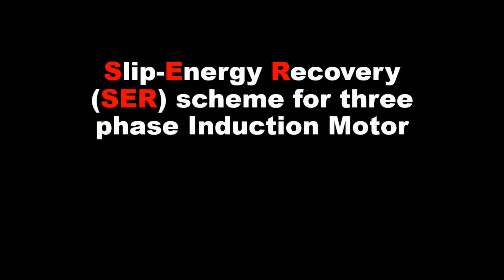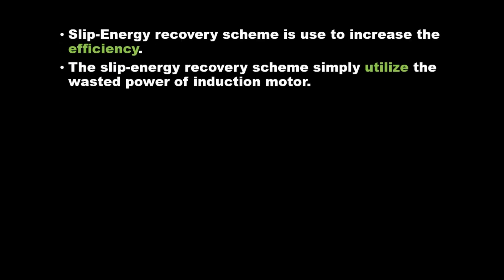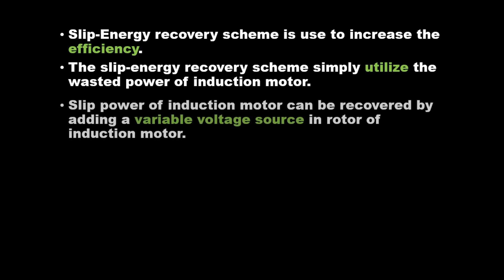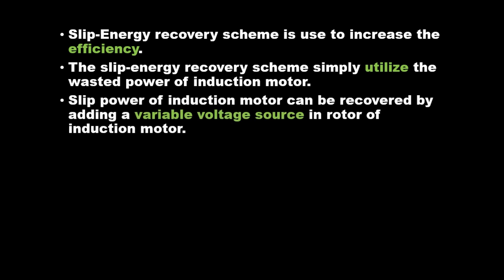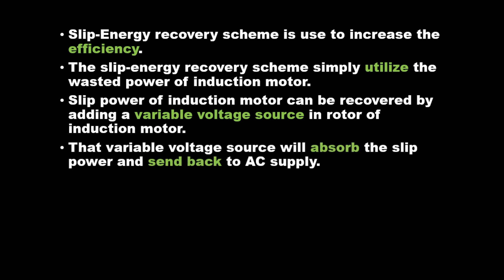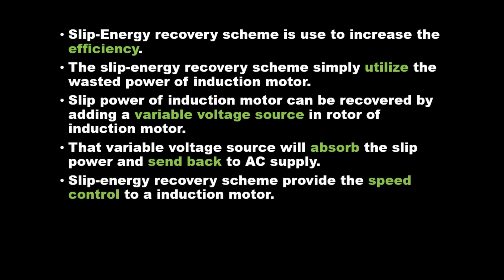The slip energy recovery scheme is used to increase efficiency. It simply utilizes the wasted power of the induction motor. Slip power of the induction motor can be recovered by adding a variable voltage source in the rotor. That variable voltage source will absorb the slip power and send it back to the AC supply, providing speed control to the induction motor.